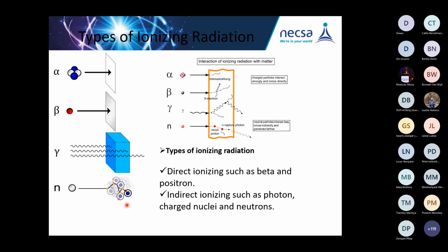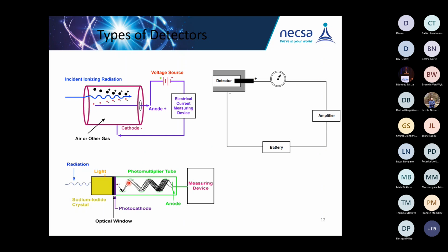And with the gammas, they've got a strong penetration. Similarly with the neutrons. And with those ones, then you know the type of the instrument. You cannot expect to measure the neutrons with the instrument which measures alpha and the beta. Similarly, the instrument that measures alpha and the beta cannot measure the neutrons. So those are the key things that we all need to understand. It doesn't mean that any radiological instrument can pick up any radiation. Radiations are classified according to their strength, and the instruments work the same.